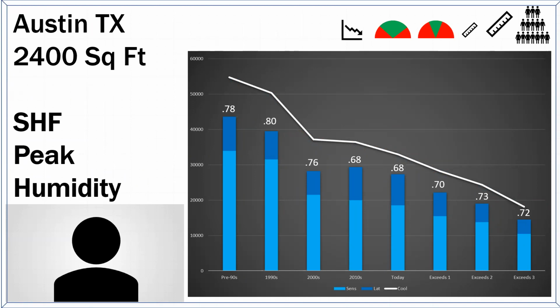When you look at Austin, Texas, you can look up on ASHRAE's weather database and TMY data, you can find what the most humid day is. And on the most humid day, this ratio I've put here is what percentage the total load on that peak humidity day is compared to the total load on the design day. So what this number means: in this old-school building, it was 0.78 to 0.8.